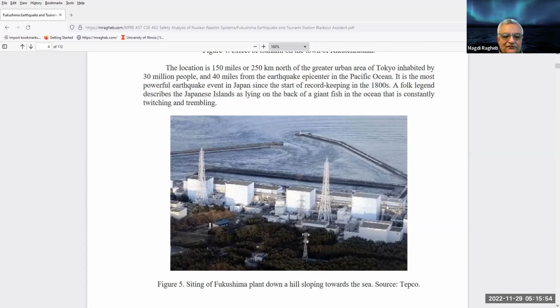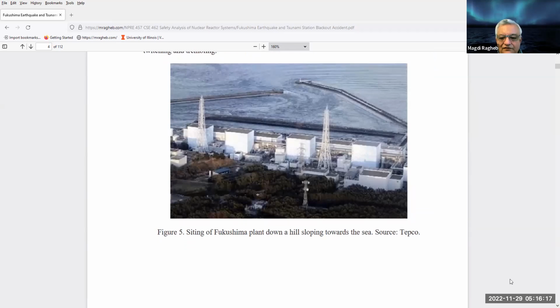The 4 units should have been designed, according to fault tree analysis and event tree analysis, to be independent of each other. In the same way as in the Brown's Ferry plant, the ducts containing the instrumentation and control cables came in from the same duct. One accident caused an accident in another unit unnecessarily in that case.